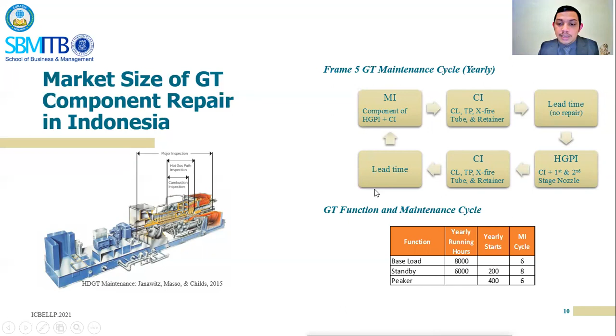Each gas turbine has its own function, usually base load, standby, or peaker. Each of these functions has its own running hours and yearly starts, which determine the major inspection cycle. The one we provide here is for base load, the most common use of gas turbines in gas turbine power plants, which has a 6-year maintenance cycle. However, for standby and peaker, there is a difference as we can see here.